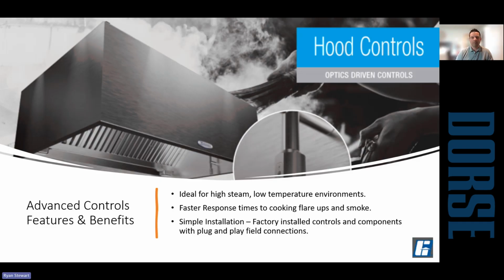To give you an example of where you might look at something like this over the baseline system, let's say you have a large charbroiler at an idle condition. So the demand control is running near its 50% speed. When you first throw a bunch of product onto the grill, it's going to have a cooling effect, all the cold product that you just put on there. But what's going to happen from a cooking standpoint is the sear is going to produce a bunch of smoke. So those sensors give that instant reaction to the smoke to start ramping the fan speed up more rapidly until the temperature sensors can catch up.